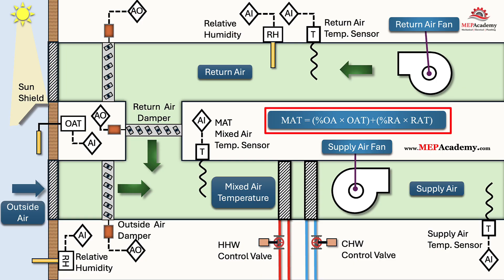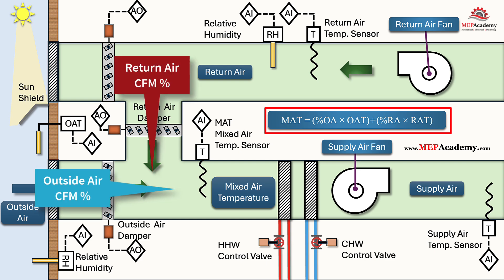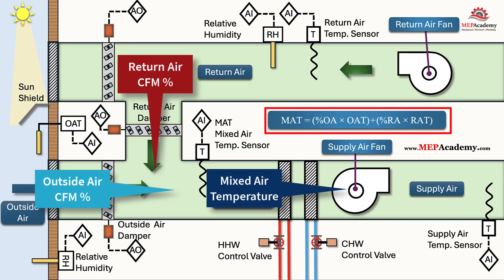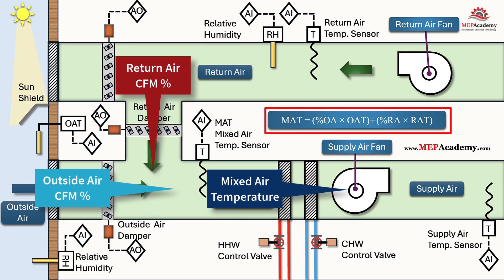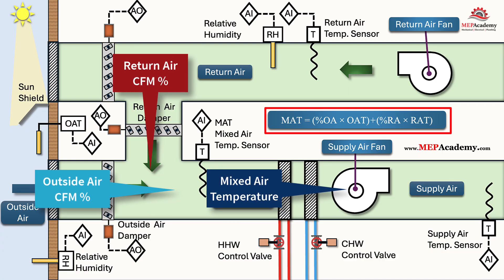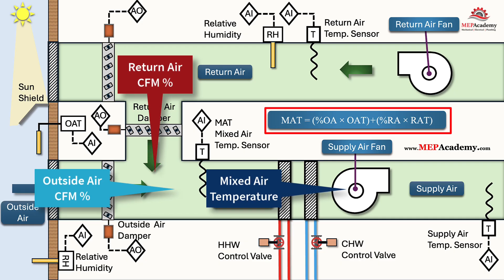This formula is based on dry bulb temperature for a dry coil. The mixed air temperature is a weighted average based on the proportion of outside air and return air: Mixed Air Temperature = (% Outside Air × Outside Air Temperature) + (% Return Air × Return Air Temperature).